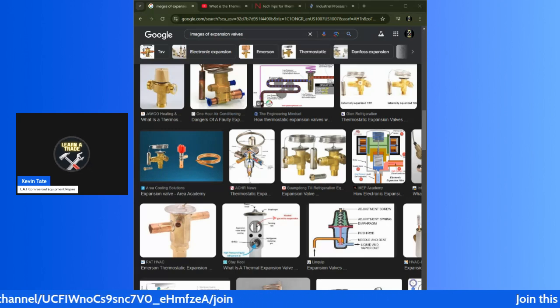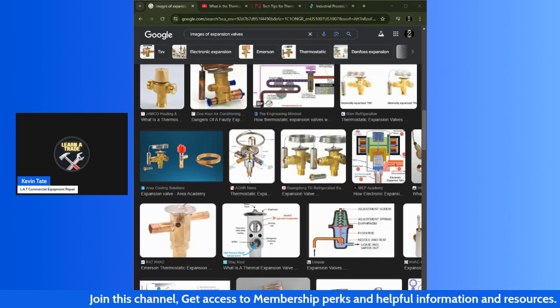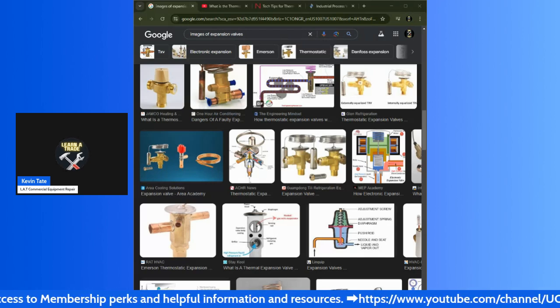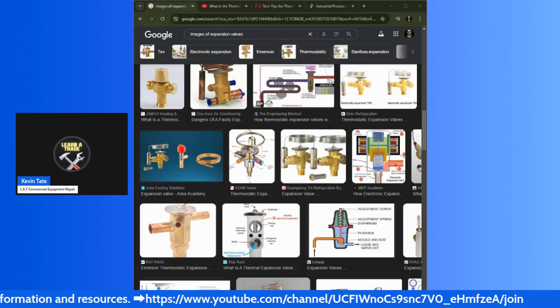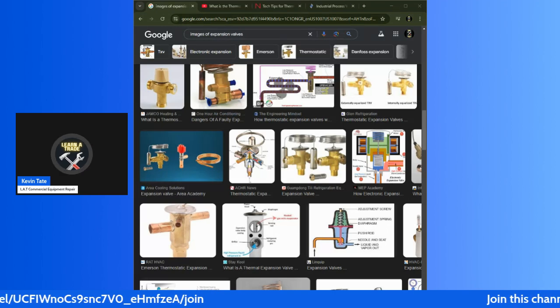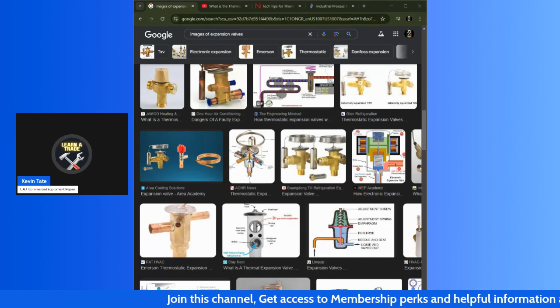These disadvantages have resulted in the automatic expansion valve being replaced by thermal expansion valves or TXV valves in most applications. The TXV valve responds to the superheat at the outlet side of the evaporator, and as a result is more responsive to the actual load, resulting in a more efficient system.